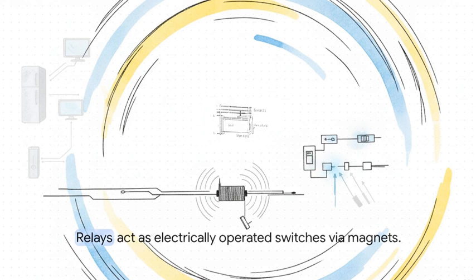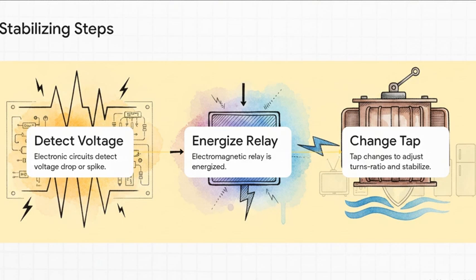Now, a relay is really just an electrically operated switch. But instead of you walking over and flipping a switch by hand, these use tiny electromagnets. When it's energized, an iron core becomes a magnet and automatically pulls down an armature. That physical movement is what switches the circuits on or off, instantly changing the tap on the autotransformer. So the most crucial point to take away is this rapid three-step dance that happens in literally the blink of an eye. First, electronic control circuits detect a sudden voltage drop or spike. Second, the correct electromagnetic relay is immediately energized. And third, the tap changes to adjust the turns ratio and stabilize the output. It's this continuous, non-stop cycle that keeps your delicate appliances perfectly safe.